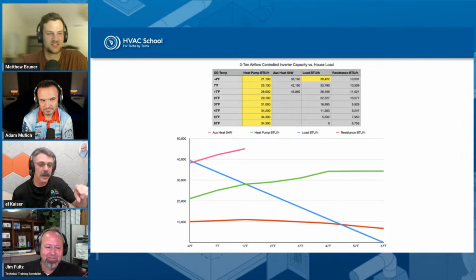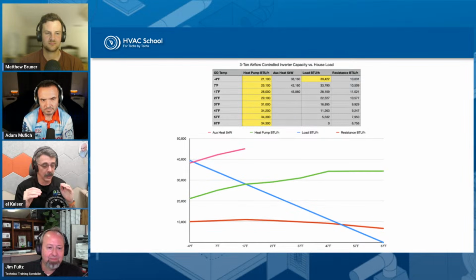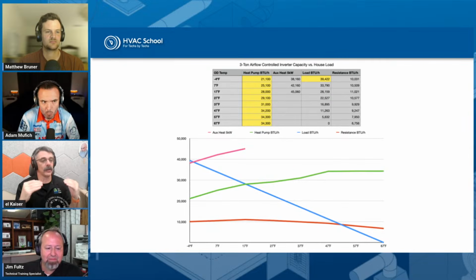Well, do you want to finish up on this slide here, Eric? So back to this slide, right there around that 17 degree mark, probably 18 degrees, if you ran a line up there, you'll notice there's a pink line up top. And that's 5 kW of resistance heat. So what happens is, with a well set up control system, now this is all dependent on how the controls are set up, when we hit that thermal balance point where the heat pump won't keep up with the demands of the house, then we bring on auxiliary heat. We're bumping that heat up just a little bit. We're adding some extra heat to that heat pump, because I still want the less expensive heat that the heat pump can produce, even though it can't keep the house at set point.